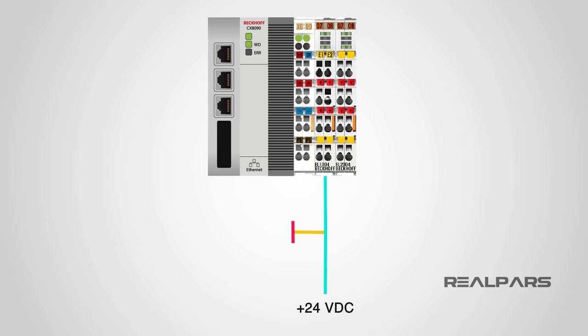So with this emergency stop switch, if the wire connected to the switch breaks, the PLC shuts down the whole system. Yes, I know, an unwanted shutdown is not what you want when a wire break happens, but this is much better than having an emergency but not being able to shut down the system. That's why you always need to use a normally closed switch for your emergency stop.